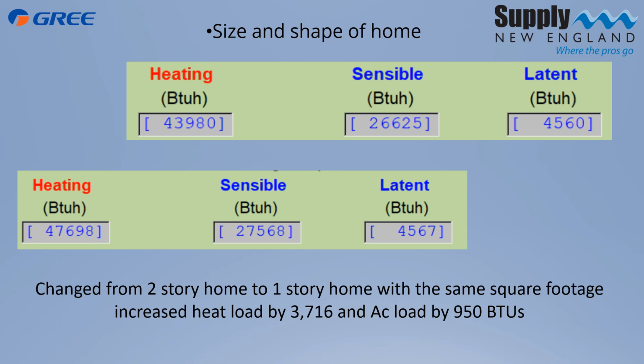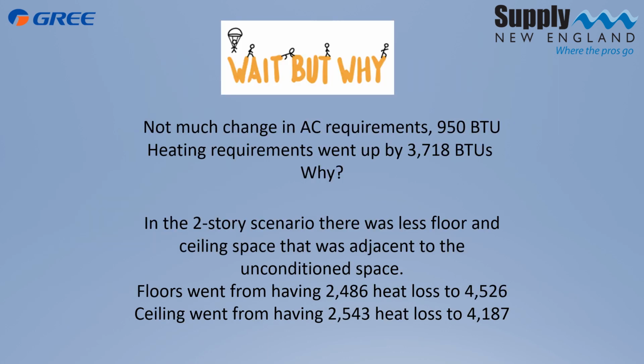The size and the shape of the home. Remember I told you we were going to be doing this. I took that same 2-story home and made it into a single-story home. And look what happens. We're increasing our heating load by almost 4,000 BTUs and our cooling load by over 900 BTUs. Now, why did that happen? Well, let's stop and think about it. What really happened is we doubled the floor space that was adjacent to a non-conditioned basement, and we doubled our ceiling space that was adjacent to a non-conditioned attic, and that's where those loads are coming from.